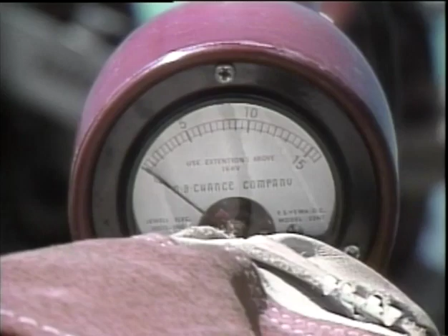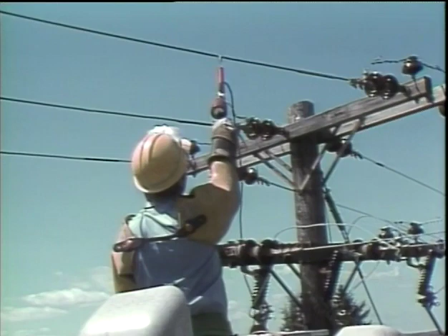With one hook on an established ground, the other is placed on the phase line you're testing. A zero reading for this line indicates there is no measurable voltage present. The phase to ground test is repeated for the other two lines on the circuit. It's important to test all the lines on the de-energized circuit you'll be working on. After the circuit has been tested, recheck the tester to be sure that it works and your results are accurate.